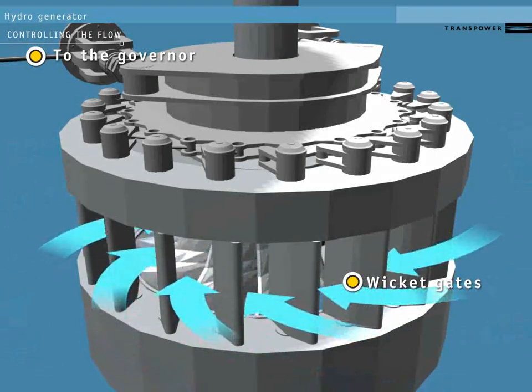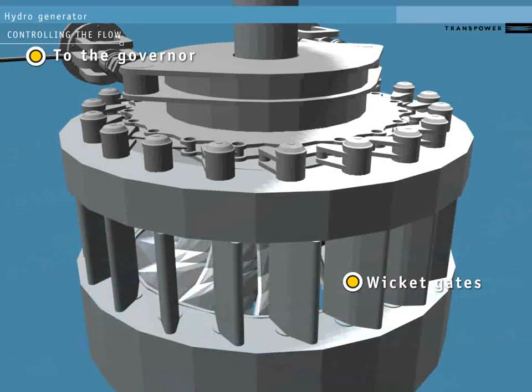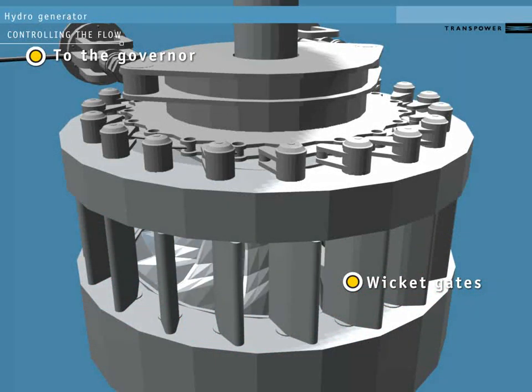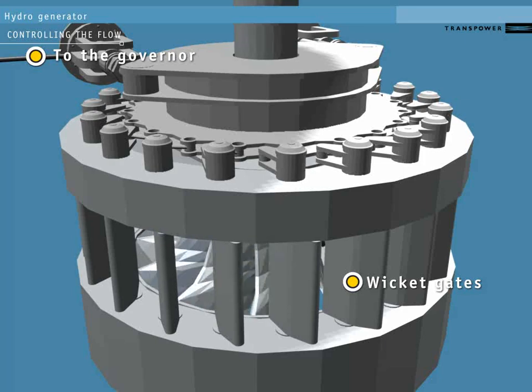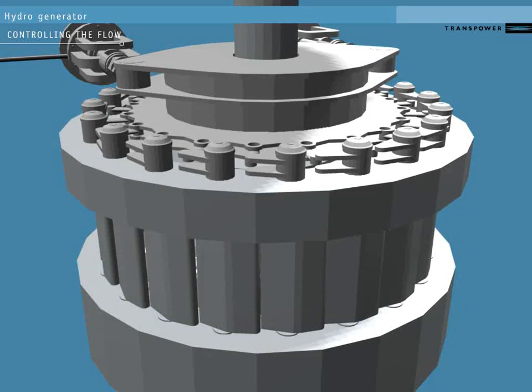A high load on the system slows the turbine. The governor system reacts by opening the gates further to speed it back up. Conversely, it will narrow the wicket gates in response to low load on the system.